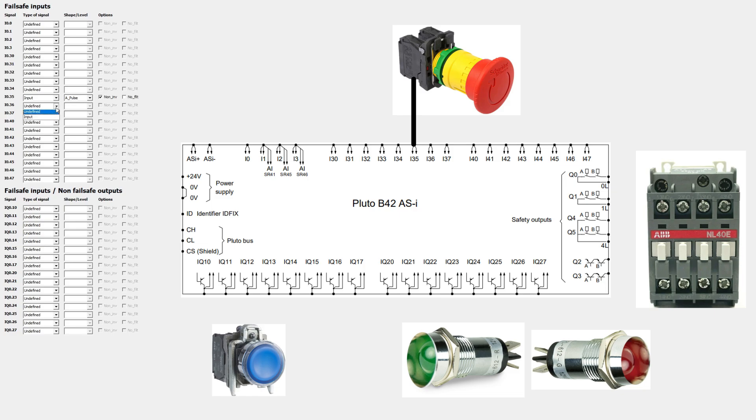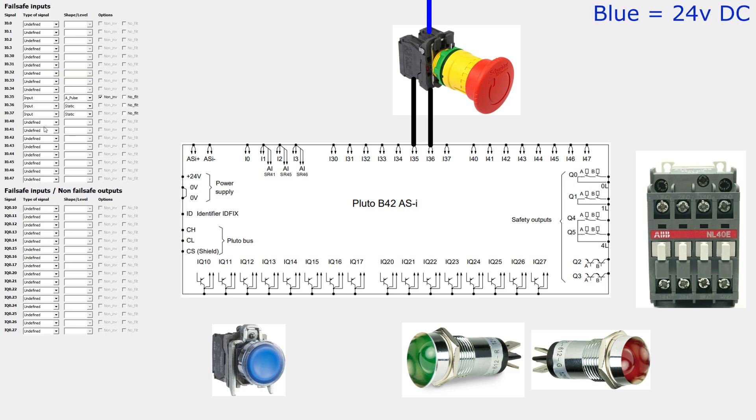Input 36 and 37 I will set to static inputs. To input 36 the other normally closed terminal from the emergency stop will be connected. And on input 37 I will wire the contactor's feedback.